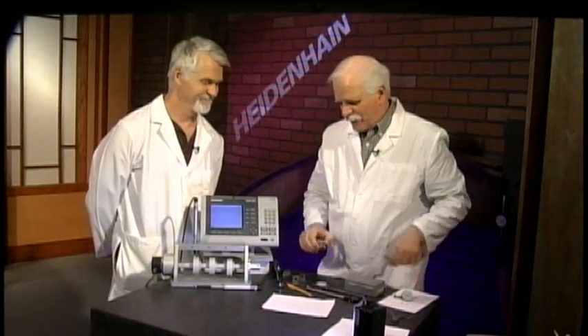Now there's always an exception. One of my favorite indicators happens to be an Interapid, Swiss made. They're made to be at a 12-degree downward angle - don't know why 12 degrees, that's just what they've decided. These will not measure linear if you have them straight out - they're made to be set at that 12-degree angle.